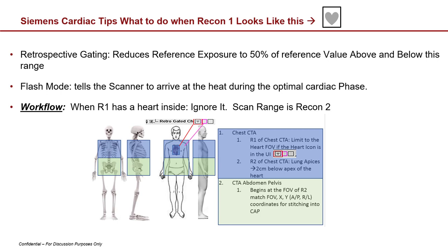In flash mode, you use the same workflow, but this time it's not to change the exposure setting — it's telling the scanner when to arrive at the heart during the optimal cardiac phase, which you allocate in the Scan Protocol Assistant (SPA) page, not in the scan card itself.